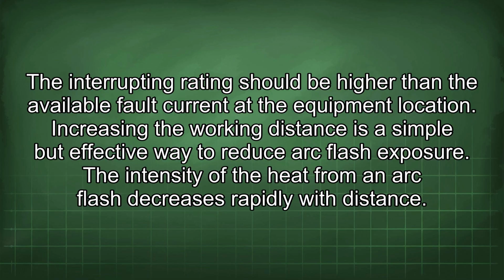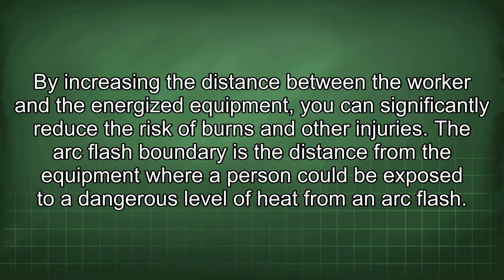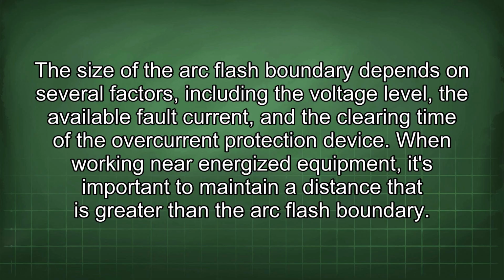Increasing the working distance is a simple but effective way to reduce arc flash exposure. The intensity of the heat from an arc flash decreases rapidly with distance. By increasing the distance between the worker and the energized equipment, you can significantly reduce the risk of burns and other injuries. The arc flash boundary is the distance from the equipment where a person could be exposed to a dangerous level of heat from an arc flash. The size of the arc flash boundary depends on several factors, including the voltage level, the available fault current, and the clearing time of the overcurrent protection device.